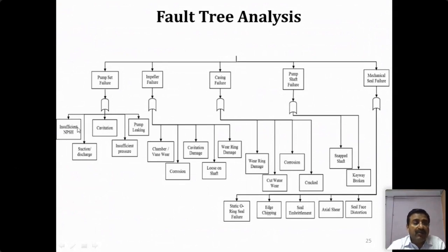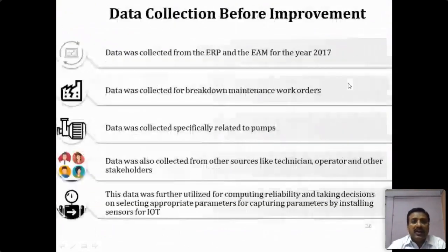Now, pump set failure will take place due to insufficient net positive suction head, suction and discharge, cavitation, insufficient pressure, pump leakage, and so on. Then the impeller failure will take place due to the chamber vane wear, corrosion, cavitation damage, loose on shaft, wear ring damage, and so on. So in this manner, the detailed fault tree analysis has been prepared. Okay. So data was collected from the ERP and the enterprise asset management module for the year 2017. Data was collected for the breakdown maintenance work orders also.